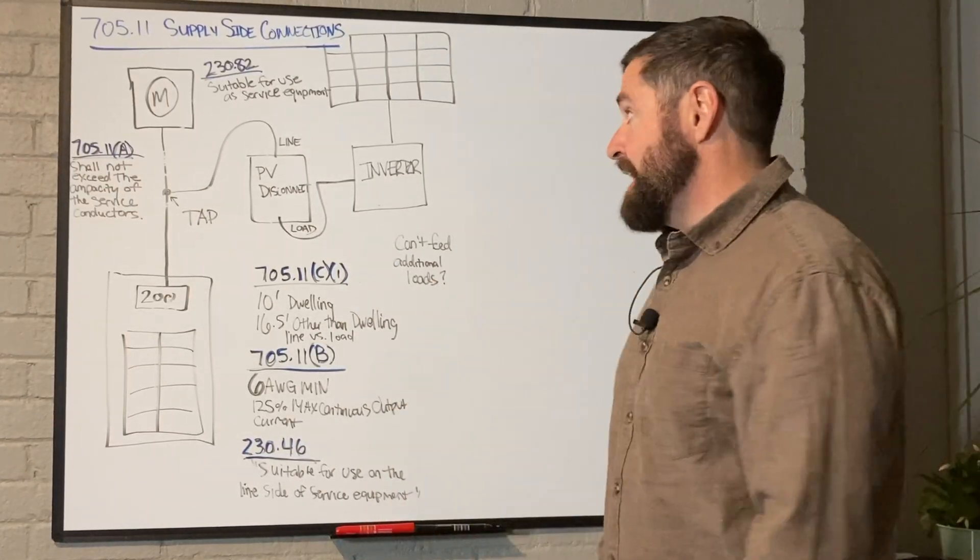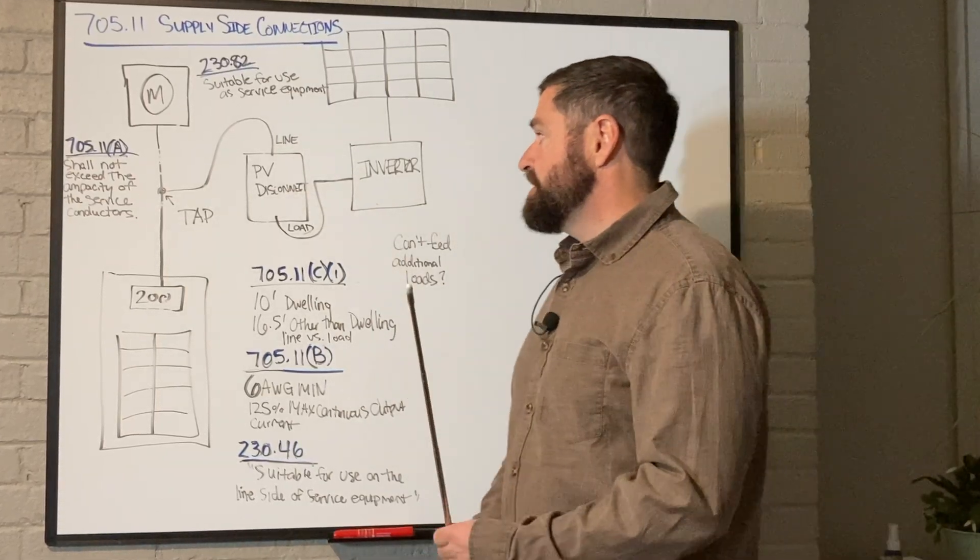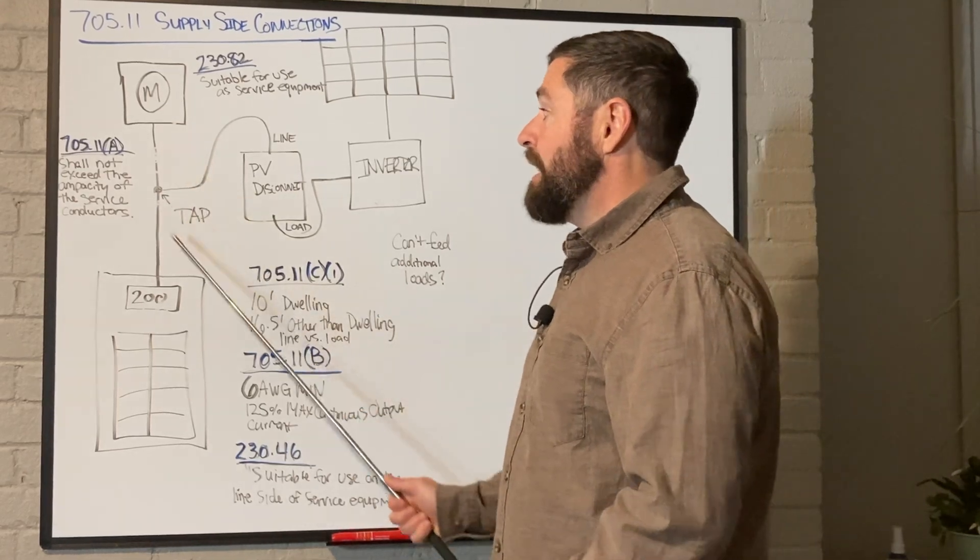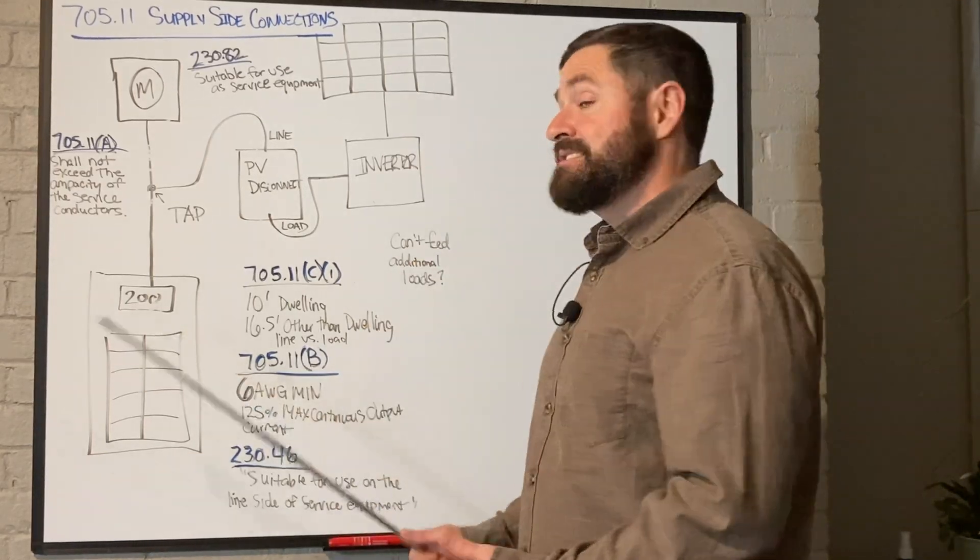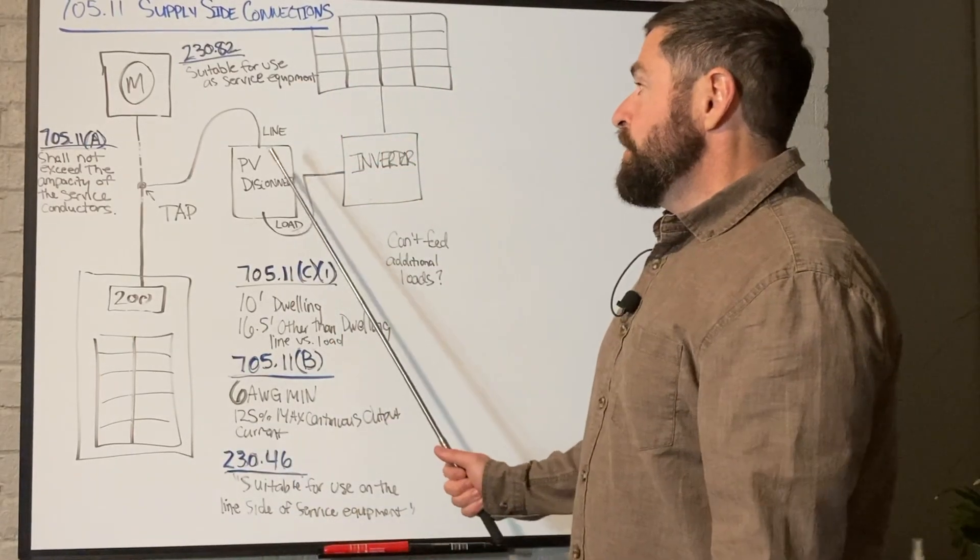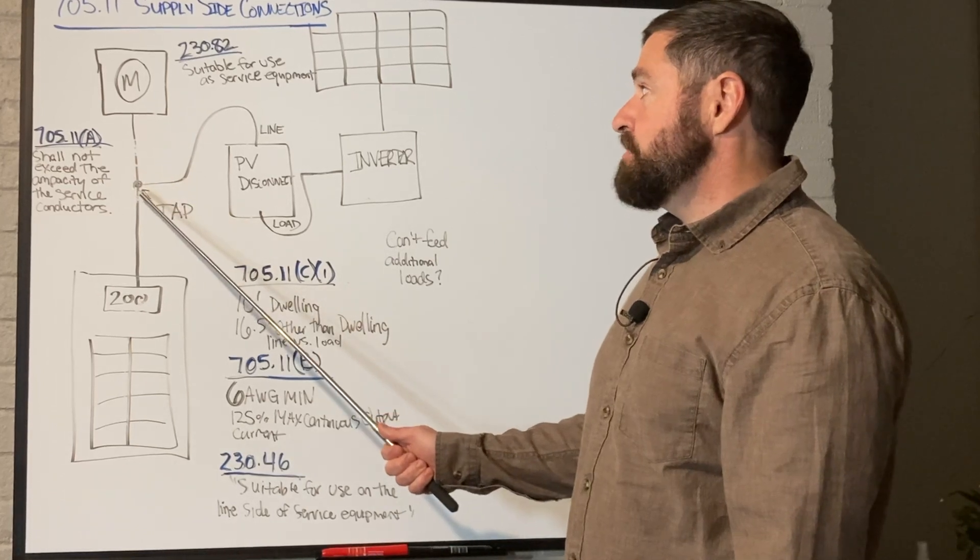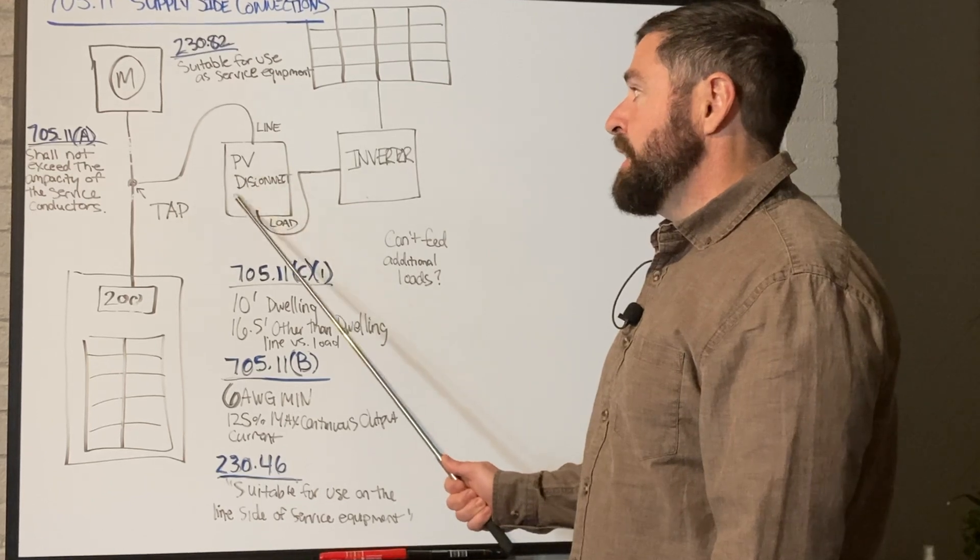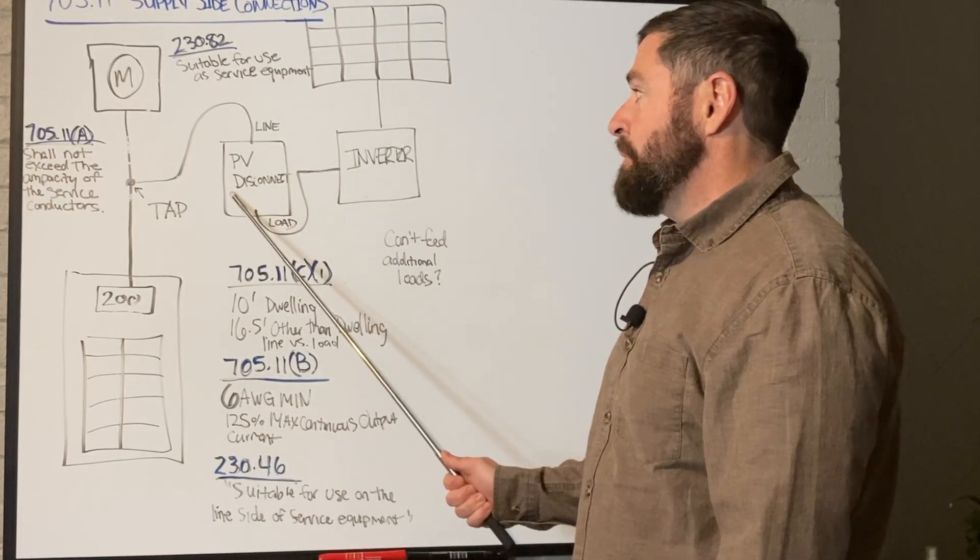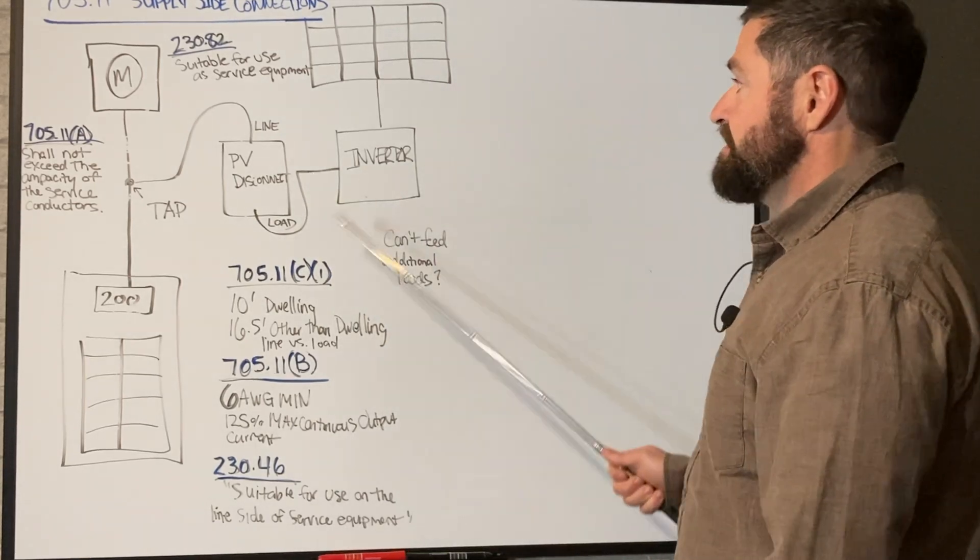And by doing so, you have a few different options here. If you're tapping just a three wire feeder as shown here, maybe you're doing it outside by the meter and the main panel's inside and all you have access to is that three wire feeder - your L1, your L2, and your neutral - you're simply just going to tap each one of those conductors, run it to the disconnect, you're going to bond your ground and neutral in this disconnect and essentially create your equipment ground which will run separated and unbonded through the rest of the system.